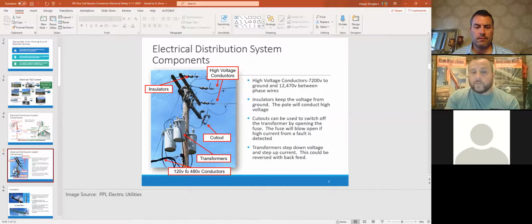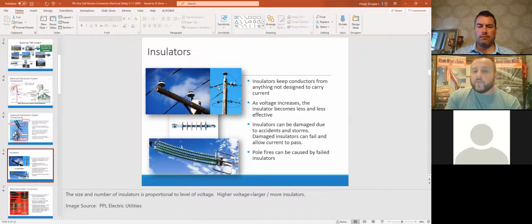As for insulators, we have porcelain ones, seen here on the top right, including the old porcelain ridge pin style. We dead-end, go up and over through another insulator, and down the other side—that's how we get around the pole when needed. On the left of this pole you'll see the newer polymer-type insulator. So we have both porcelain and polymer insulators. The ridge pin on top holds the wire fastened through the insulator, running straight through but never contacting the pole itself.